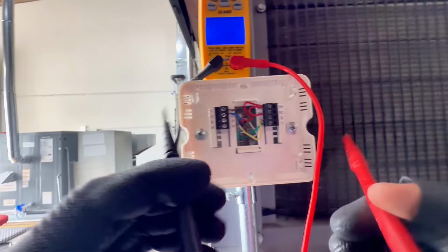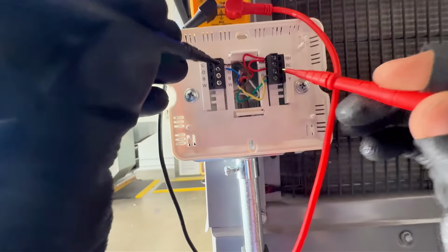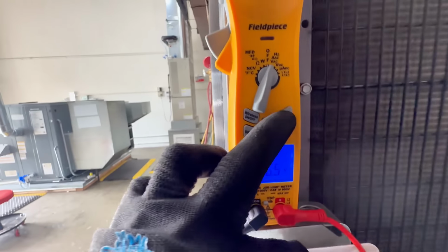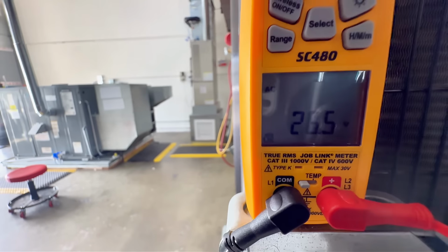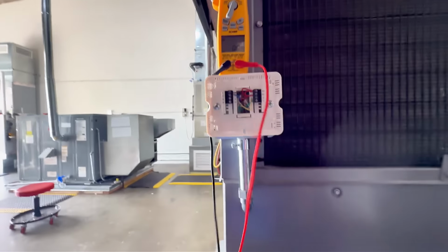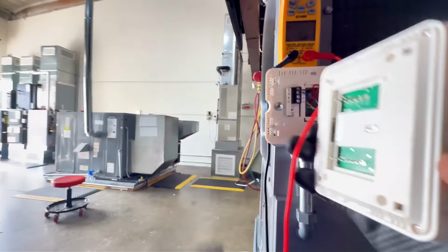I'm gonna check my leads. I'm gonna put it on VAC. I'm gonna check common and my R. And sure enough, without the light, you see right there, 24 volts. So I have power coming to the back of my plate. So now I'm gonna go ahead and put this back.